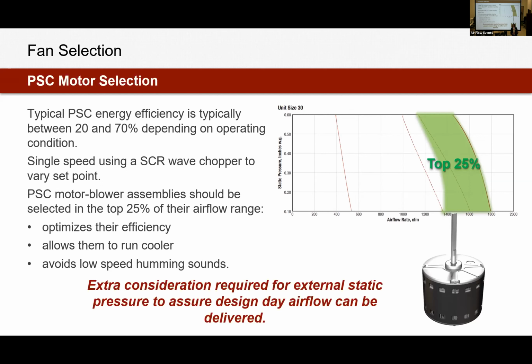Also, if you're running at lower flows on the PSC, sound is usually a huge issue. They hum a lot. They make a lot of noise. I've been on too many job sites where that was the issue, that they were running it too low and they were noisy. You also have to, when sizing and selecting with the PSC, be even more mindful about your static pressure, because we can see in this fan curve here, the fan curves drop off really quickly as our static pressure starts to increase. So, you know, you're throwing water coils, maybe you're throwing silencers on the boxes, pressure's rising, and that possible airflow is just gonna keep dropping.